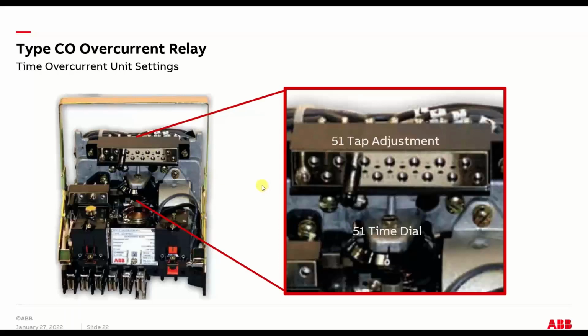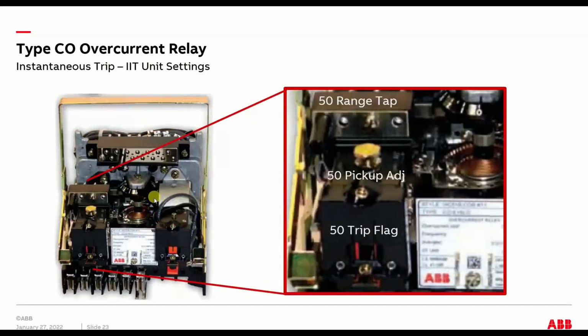So just as a quick tutorial on how to read these things. They look complicated, and if you walk up to one, it's very unclear what they're set to and what they do. So I just want to do a really quick walkthrough on how to look at an old electromechanical relay and see what the settings are. For the time overcurrent, there's a tap and a time dial. The tap is literally a tap. It's little holes with a screw element that you can change among all these predetermined tap values, and that'll set the pickup of the relay. And the time dial is literally just a little dial, with no notches, no detents. It's a continuous dial that goes from, say, 0.5 to 11, and you spin it until it meets the setting. That's it.